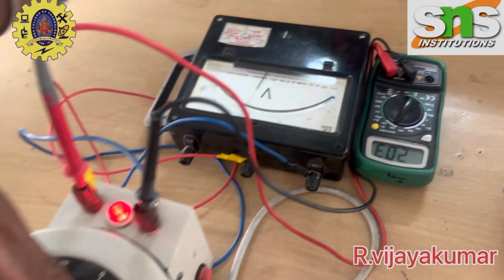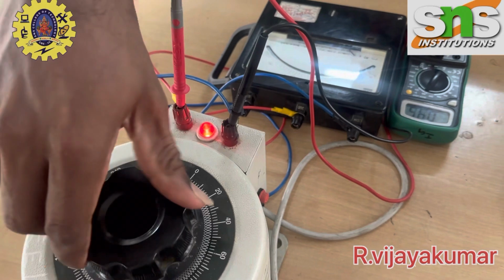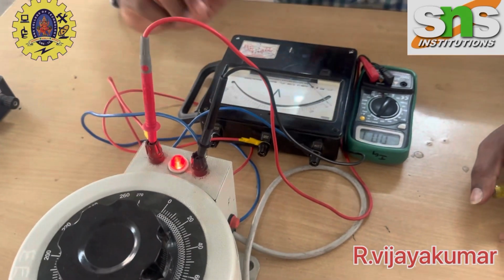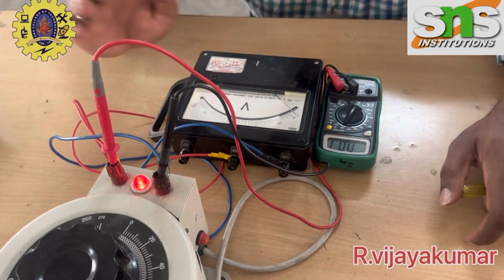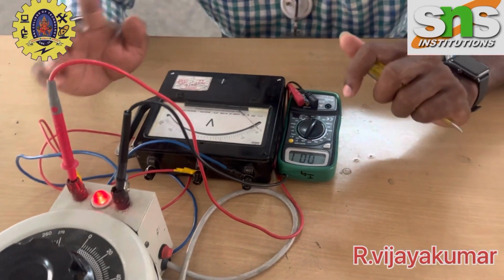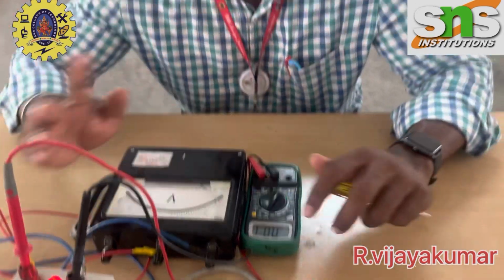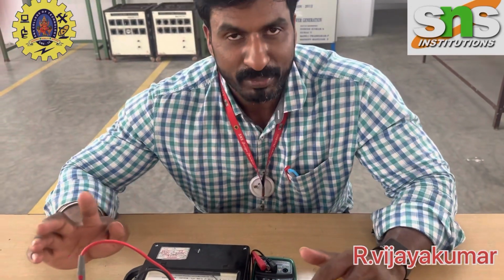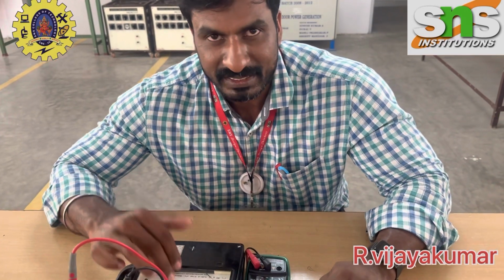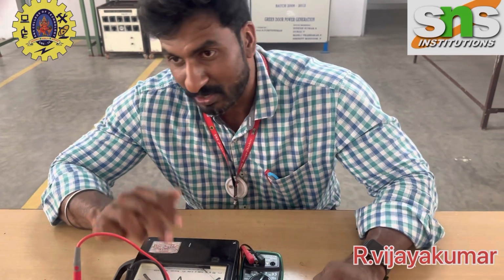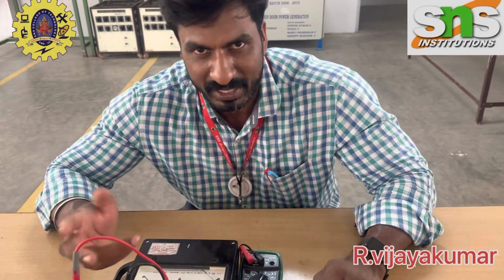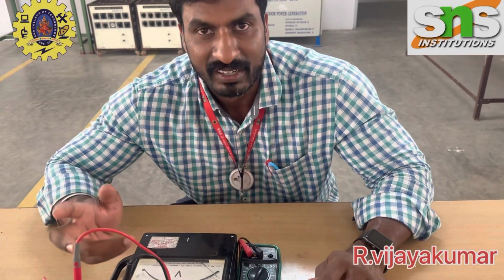This is calibration as well as correcting the meter. Every 1 or 2 months, we need to calibrate it against a normal calibrated meter. This is very important, because this meter alone decides whether the motor efficiency or other electrical parameters are correct or wrong.